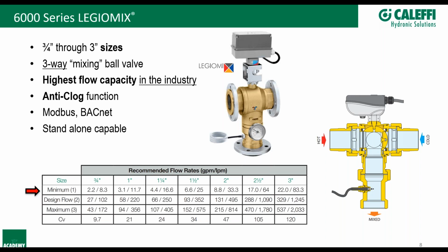So again, sizing is very important with any valve, especially mixing valves, because for many years, especially with thermostatics, it was very easy to undersize the mixing valve. The obvious downside to undersizing is that when you reach demand or design flow rates, you're going to get really high pressure drops through that valve, and then a lot of complaints that you're not getting the water flow you need out of your fixtures. So, great question, get as close to the design size as possible.